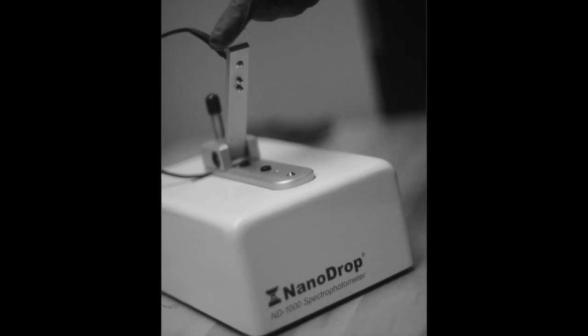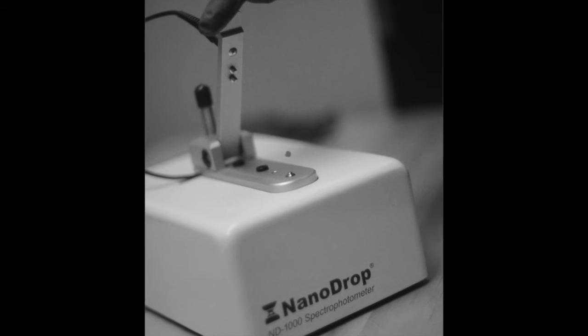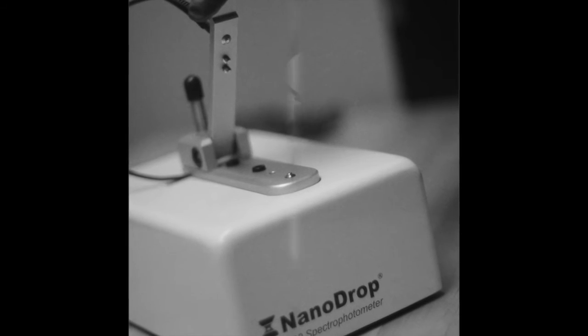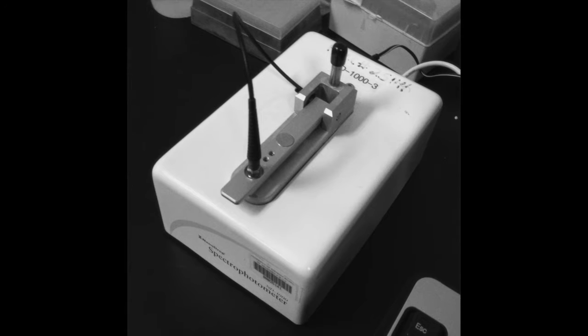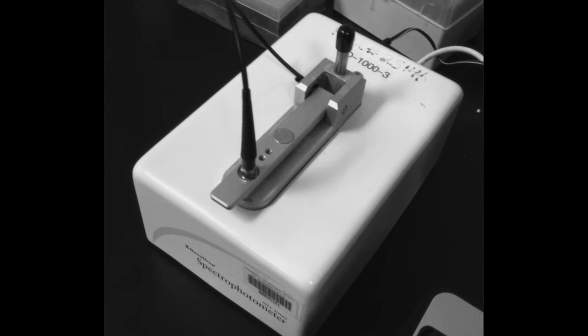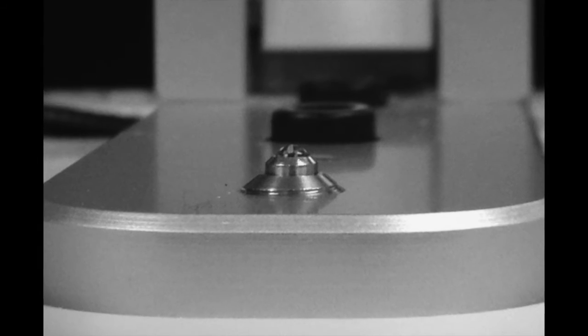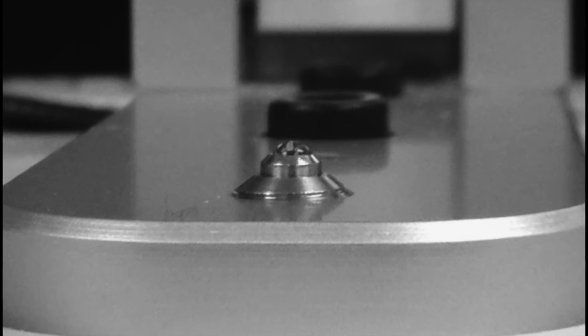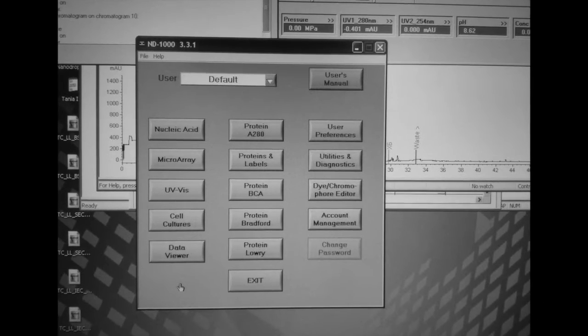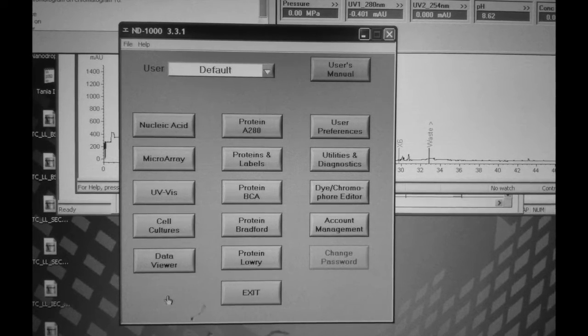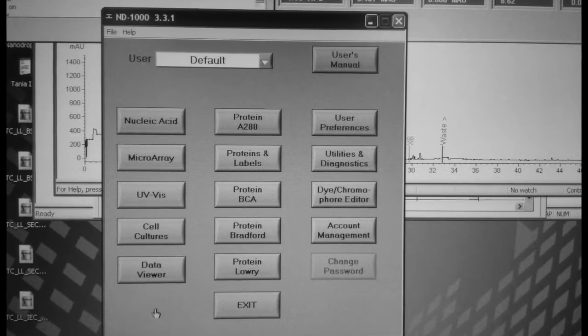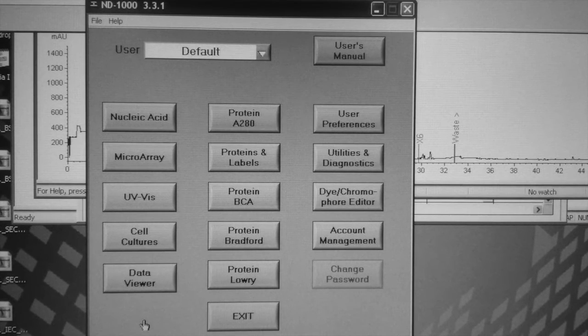The NanoDrop ND1000 works just like the Genesys, but it only needs 1 or 2 microliters of the sample. The secret is a special pedestal, where the drop is placed directly onto the tiny window. When the pedestal arm is lowered, surface tension forms a 1mm bridge for the light beam to travel through. The NanoDrop is operated through an electronic computer, which allows the machine to apply the right calculations to an accurate measurement. This lab works with nucleic acids and proteins.